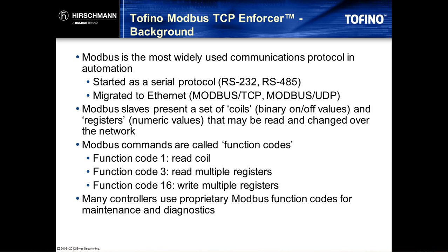Modbus controllers, so-called Modbus slave devices, allow Modbus masters to read and write binary values called coils and also numeric values called registers. And these values are accessed using commands called function codes. There's a set of function codes that are publicly documented and widely supported by most Modbus capable devices, and there's a wide range of proprietary Modbus function codes that vary depending on the specific device and vendor.